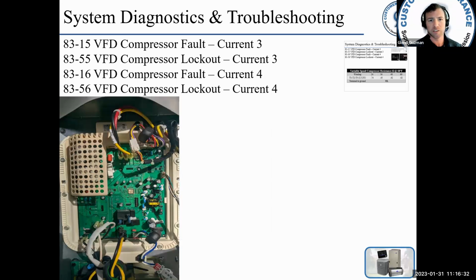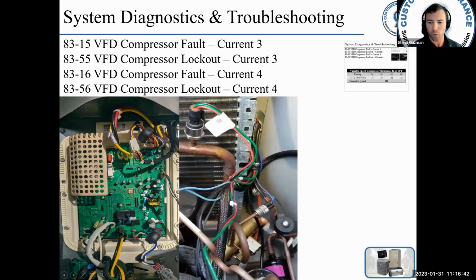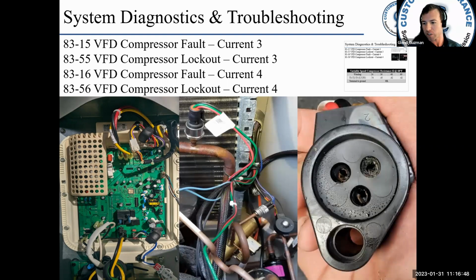Look at the connections. Like I said, what causes high current? Poor connections. Check your connections at your VFD. Check your wiring harness, your high voltage wiring harness going to the compressor. Take a look at the compressor plug.